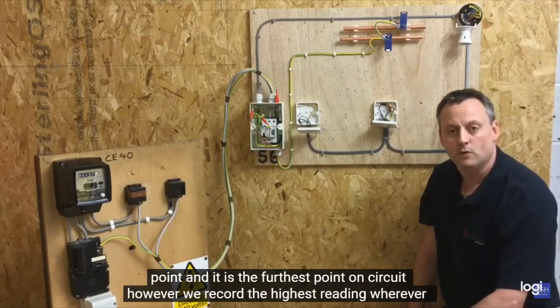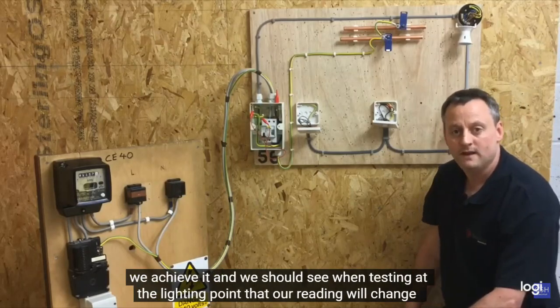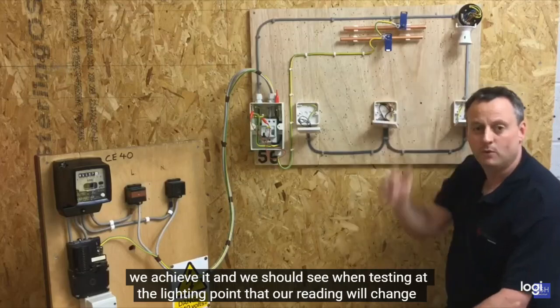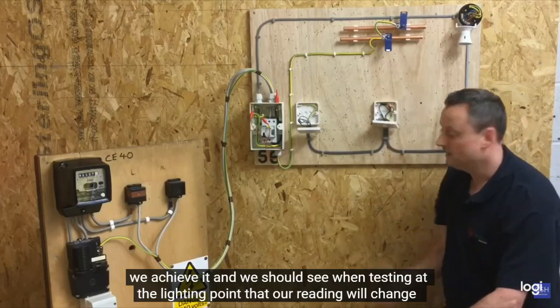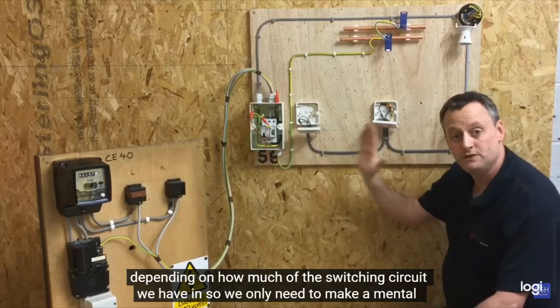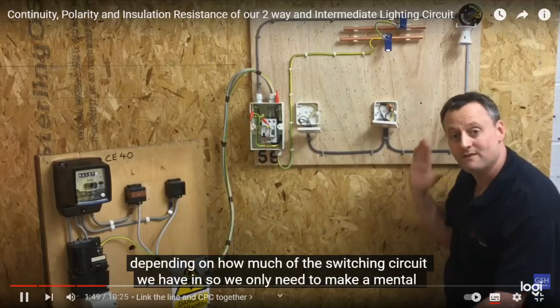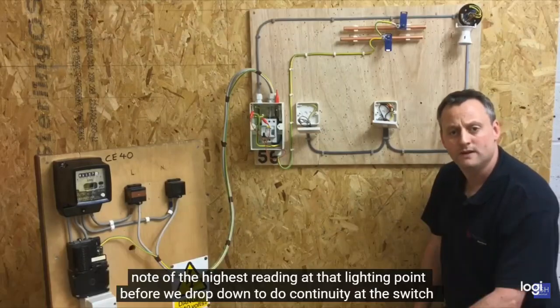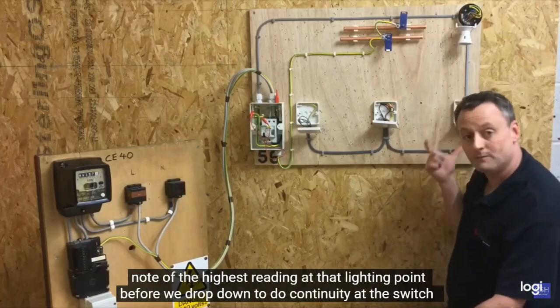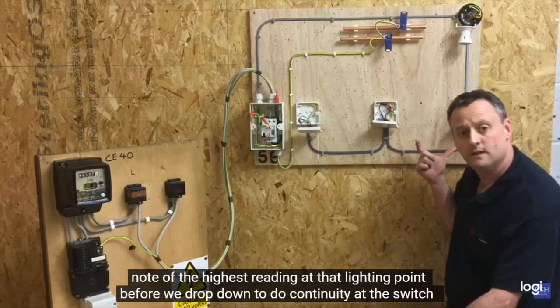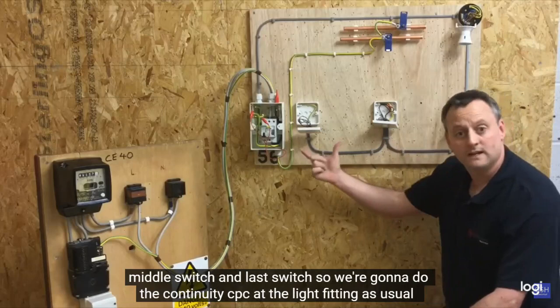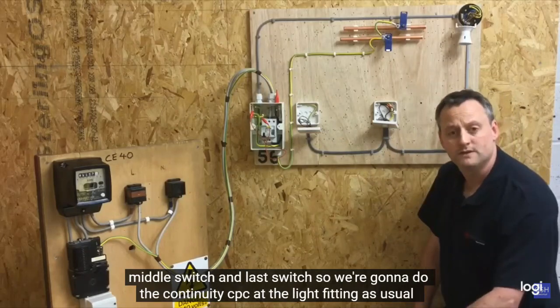So we aim to make a mental note of the highest reading at that lighting point before we drop down to continuity at the switch, middle switch, and last switch. We need to do the same thing as usual. Remember the highest reading, drop down to each switch in turn. Again, remember the highest reading, we record whichever reading that is.